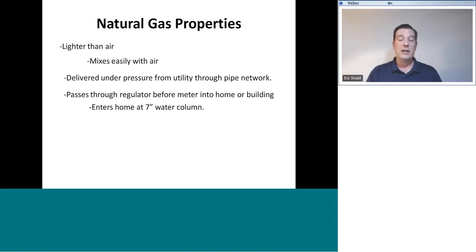So this amount of pressure, 7 inches of water column, will push water up a column 7 inches tall. To give you a comparison to pounds per square inch, which most folks are a lot more familiar with, such as the tire pressure in your car or your bicycle, or refrigerant gauge pressure, we measure those in pounds per square inch, PSI. And that means the equivalent pressure of a weight pressing down on 1 square inch surface.